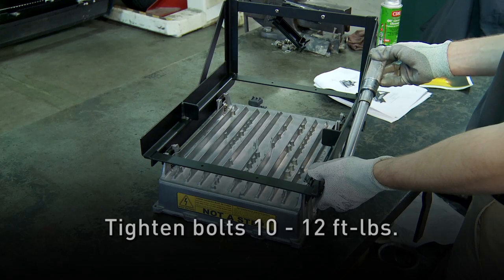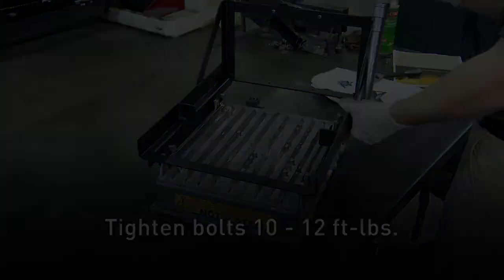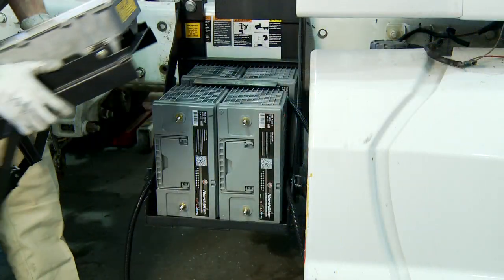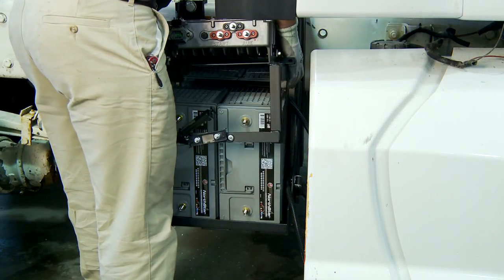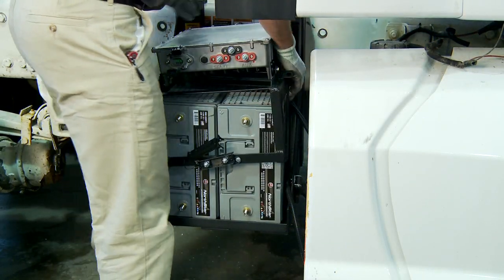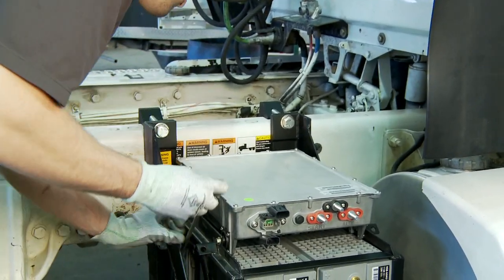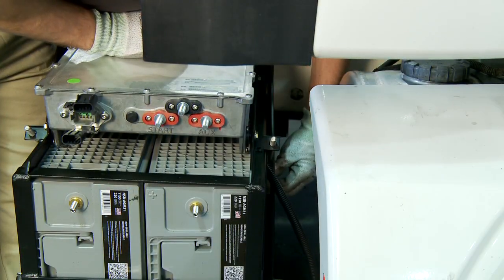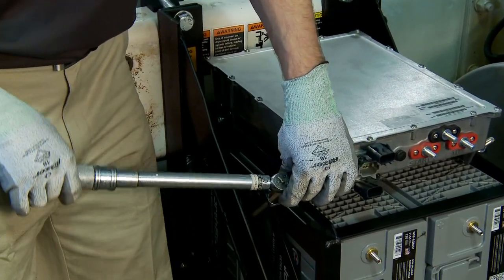Tighten the bolts to between 10 and 12 foot-pounds. Then place batteries 3 and 4 and attach the PMM and the battery hold-down bracket with PMM installed onto the battery box. The battery hold-down is attached using supplied J-bolts. Tighten the nuts on the J-bolts to the torque specified in the installation manual.